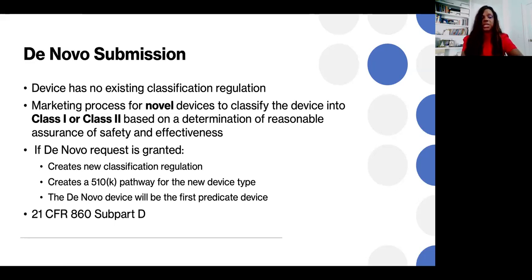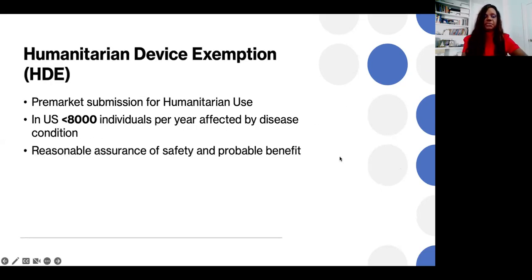So the review is based on a determination of a reasonable assurance of safety and effectiveness. And then if your de novo request is granted, this now creates a new classification regulation and a 510(k) pathway for subsequent devices of the same type. So your de novo device then would be the first predicate device for the other companies that are going to come along. And if you want to look at the de novo requirements, it's codified under 21 CFR 860 subpart D. Next slide, please. And lastly, we want to talk about the humanitarian device exemption, or an HDE.